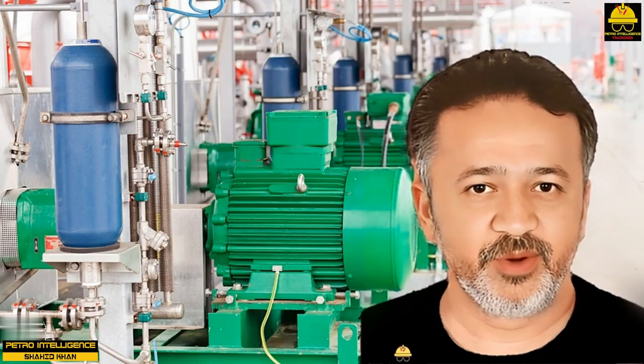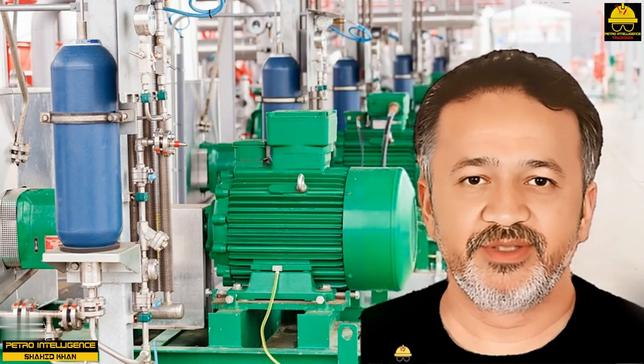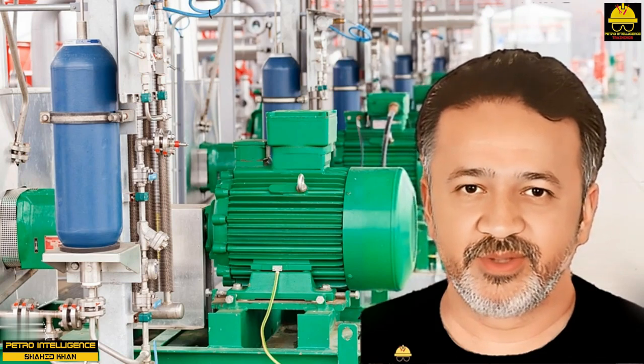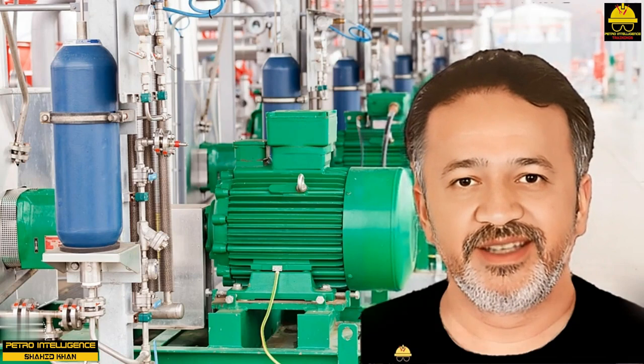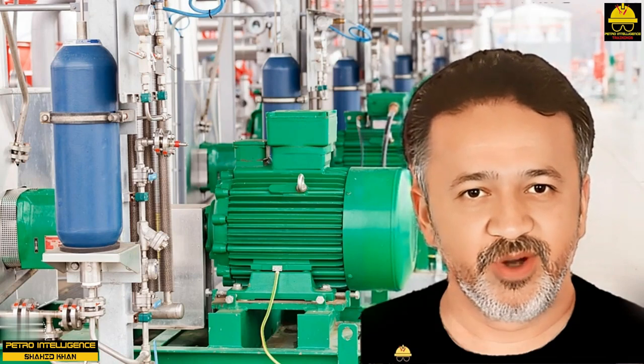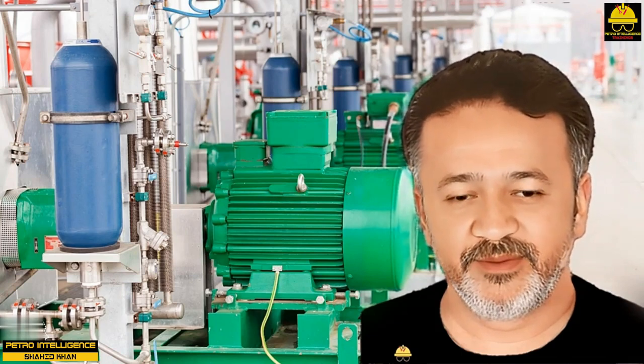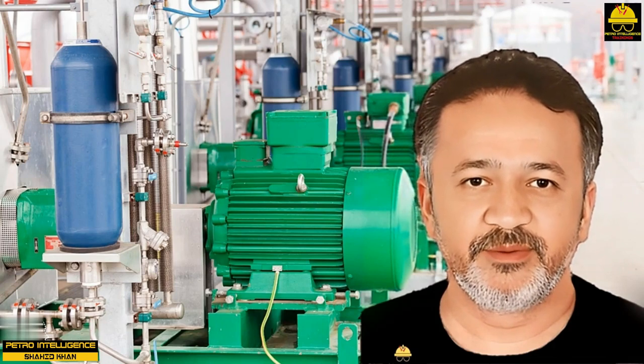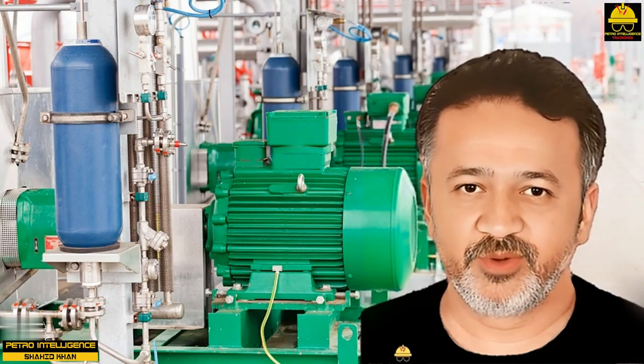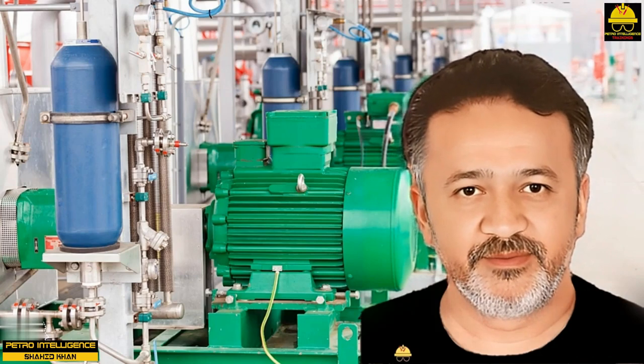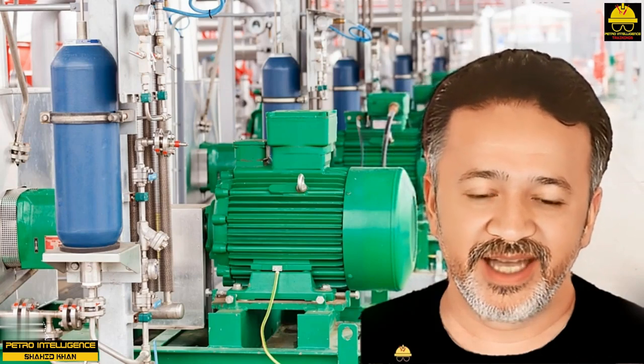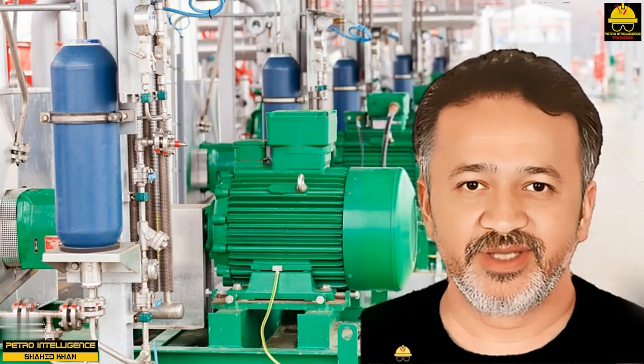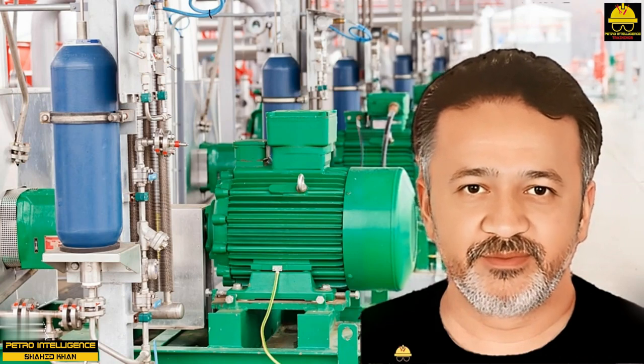In a centrifugal pump, liquids must be pushed, not sucked or pulled, into the impellers. Suction head is a term used to describe the pressure required to force liquid into a pump. A centrifugal pump must be primed or liquid full before the pump can be engaged. Net positive suction head, NPSH, usually is calculated in feet of liquid.